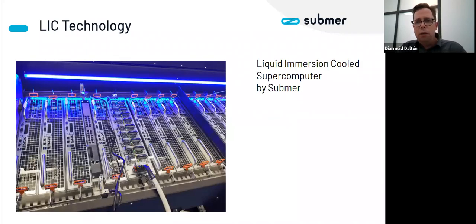Okay, maybe the other side of things. Here we have an image of a typical HPC installation, this one specifically with Open Compute hardware, but essentially very similar nodes. Actually, it's the identical node that we were showing before in the render. So 8 GPU nodes with 2 CPUs, fully submerged in one of our SmartPod X units. This is the larger version, the XL, which can host up to 42 OU and 45U of 19-inch hardware, and dissipate up to 100 kW with warm water loops and ambient air. We'll go into more detail on that in a while.